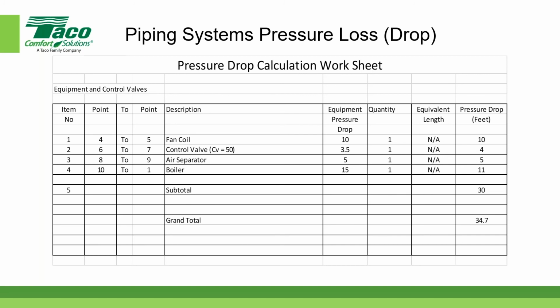So when you made the choice of pipe size, you used 8 feet per second. Was that a random number, or why'd you do that? Well, you know, most hydronic systems are designed for a range of velocities anywhere from 6 to 10 feet per second. And the most common value for hot water and chilled water heating and cooling systems is around 8 feet per second. So I decided, it's a bit subjective, I wanted to have a velocity of less than 8 feet per second.